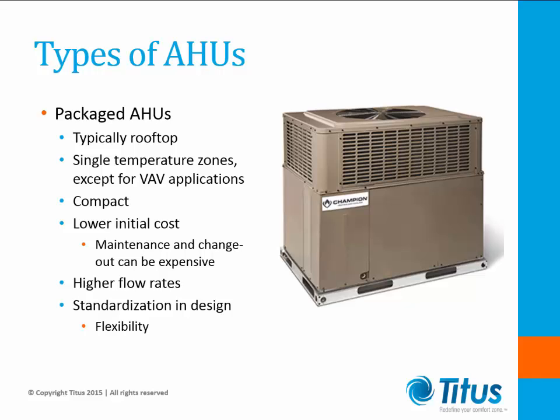Another type of AHU would be a packaged unit. Packaged units are common in smaller buildings and found on rooftops. Packaged units contain fans, coils, filters, and dampers in a single casing, and possibly even include compressors, gas burners, electric heating coils, and heat pump coils. Packaged units tend to treat single temperature zones except for VAV applications. Because of their compactness, packaged units have a lower initial cost. Packaged air handling units warrant extensive maintenance, and changeout could possibly be expensive as well. Over the years, performance and reliability has progressed, and quality can be found now in those units.